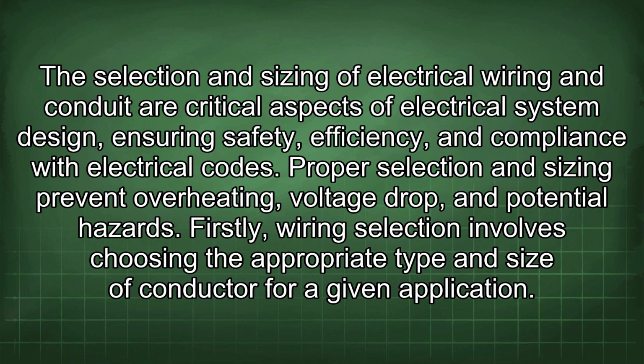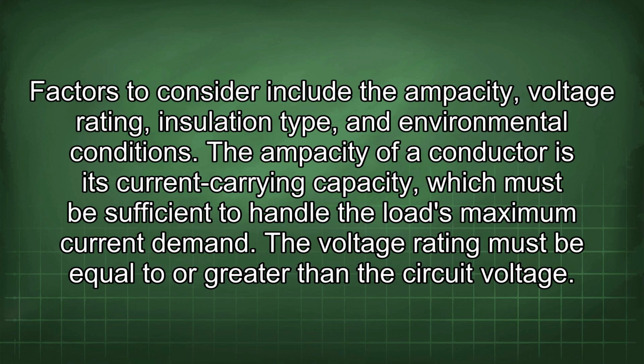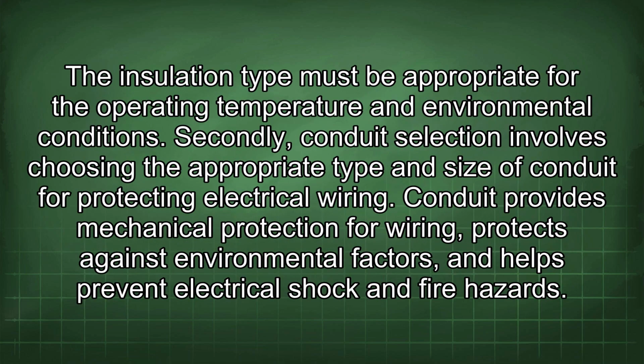Proper selection and sizing prevent overheating, voltage drop, and potential hazards. Firstly, wiring selection involves choosing the appropriate type and size of conductor for a given application. Factors to consider include the ampacity, voltage rating, insulation type, and environmental conditions. The ampacity of a conductor is its current carrying capacity, which must be sufficient to handle the load's maximum current demand. The voltage rating must be equal to or greater than the circuit voltage. The insulation type must be appropriate for the operating temperature and environmental conditions.